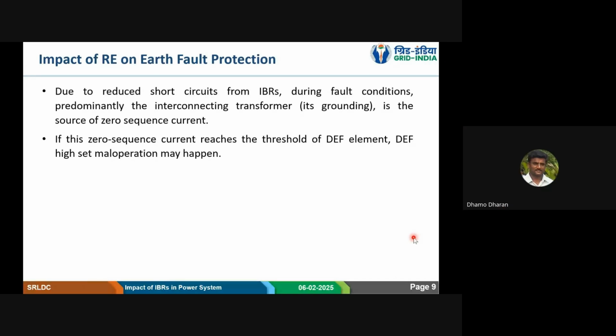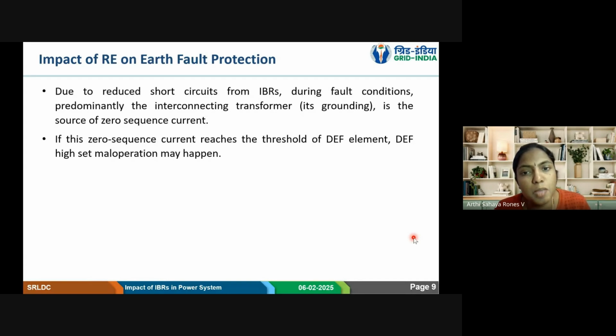So the conventional system will contribute high fault current, whereas the IBRs, they'll contribute very limited short circuit current. Because of that, during the fault conditions, the interconnecting transformers, IDTs of the IBRs, they are grounded. There is some looping of zero sequence current through this interconnecting transformer, and that contributes to the presence of zero sequence current. So when a fault happens, we expect the negative sequence current to be there from the generator so that we can detect that and clear the protection. But in this case, there is no negative sequence current. What we are seeing is the zero sequence current. Because of this zero sequence current, the earth fault protections, which are very sensitively set, they can maloperate.